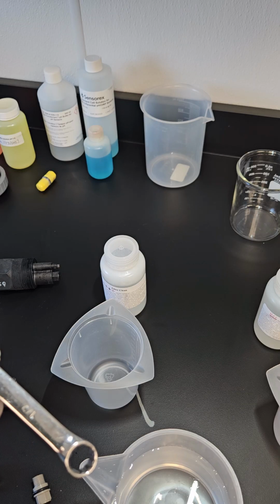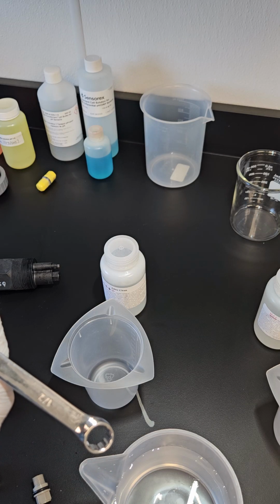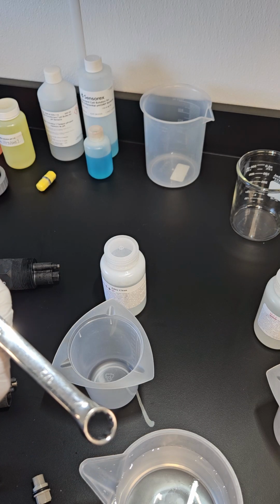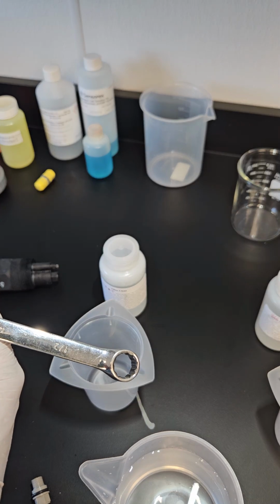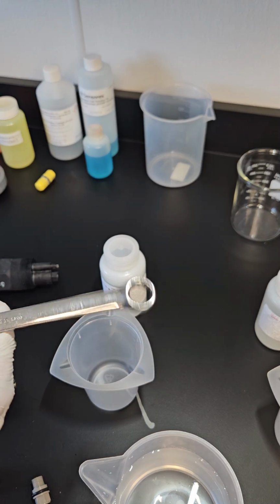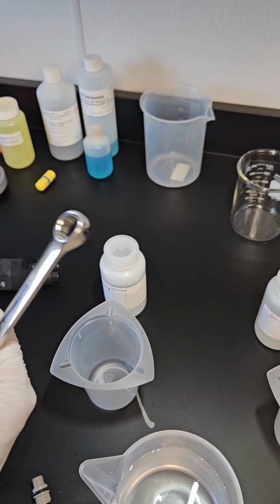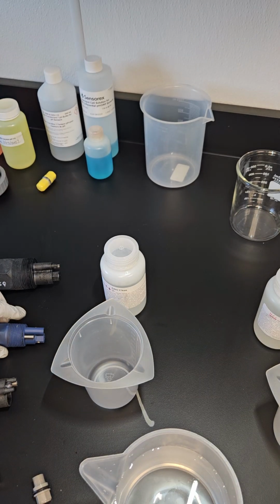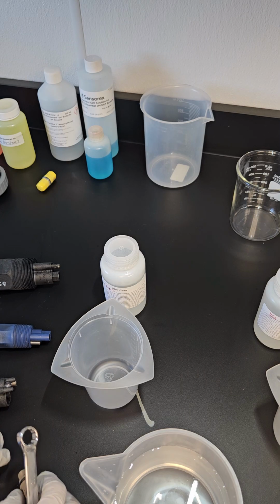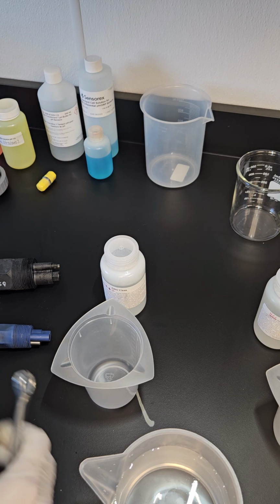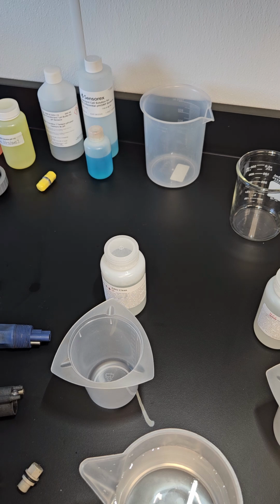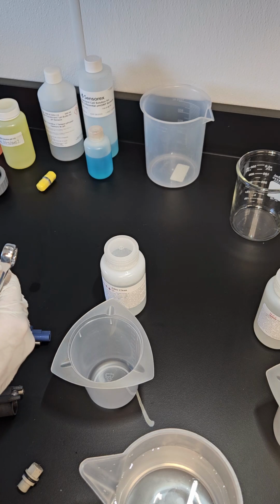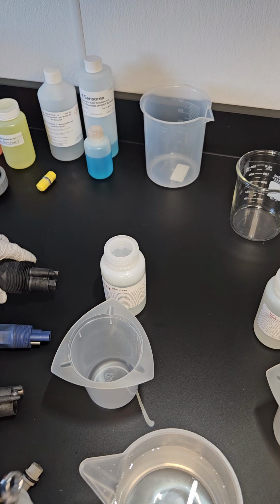A large Phillips screwdriver may work, but if it's already loosened up, sometimes the wrench is needed. Now, it only needs to be finger tight when you retighten them. The gaskets do the sealing. It doesn't need a lot of pressure. So those are the three salt bridges again. The 15 millimeter again on this one. The other one uses a 9/16. I usually use sockets on these because you're less likely to bump into the crystal or the bulb when you're using a socket versus an actual open-end wrench on those.